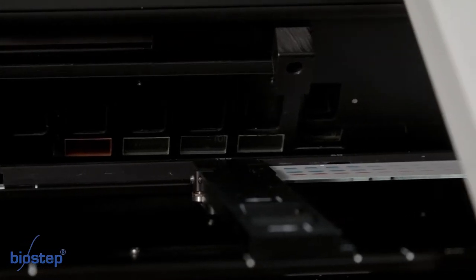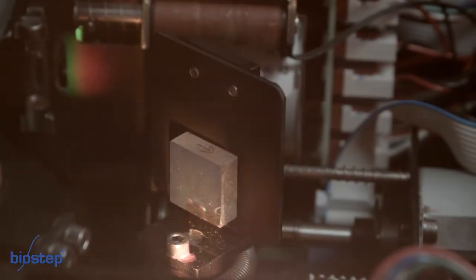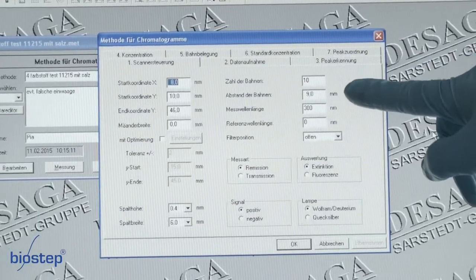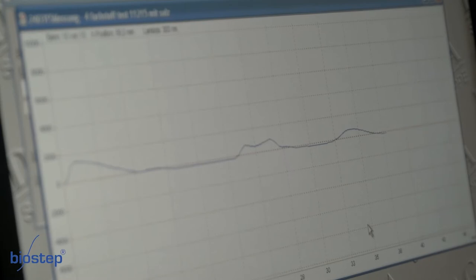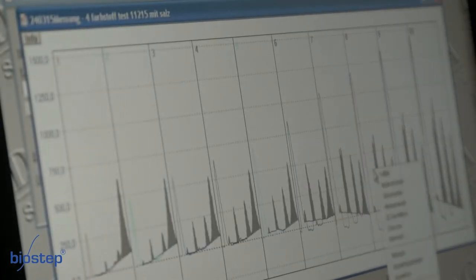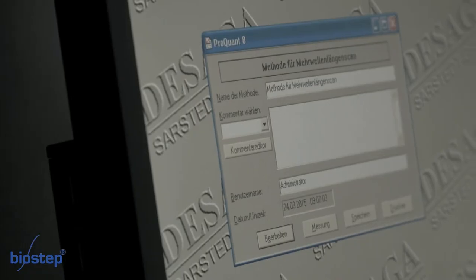A chromatogram is recorded at a desired measurement wavelength and shows the course of absorption or fluorescence of one or more lanes graphically. Recording a spectrum means that the course of absorption or fluorescence of one spot is measured in a desired wavelength range and graphically displayed.